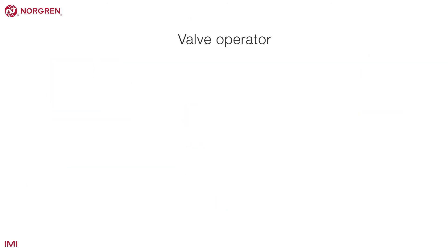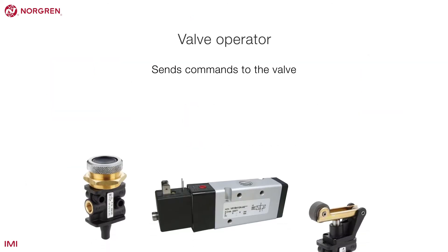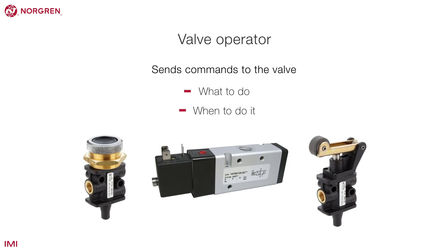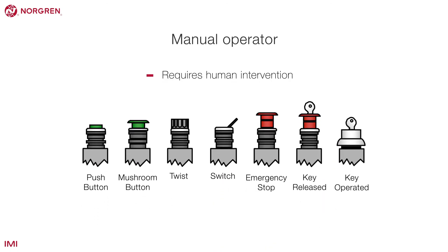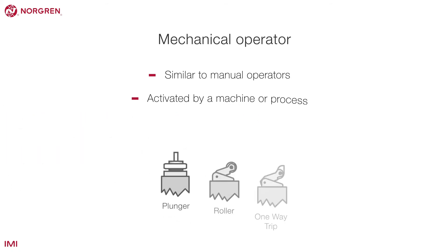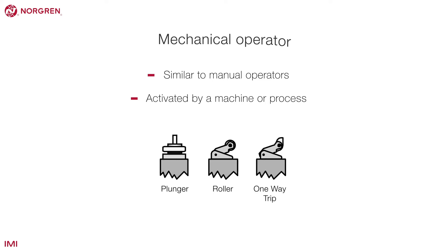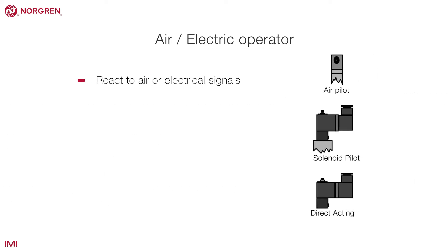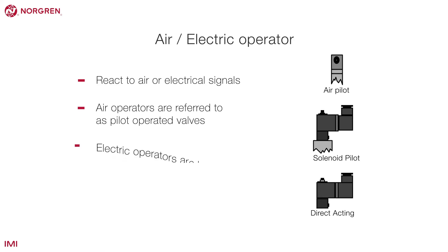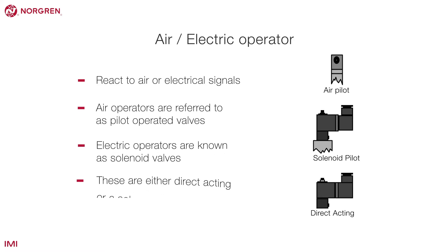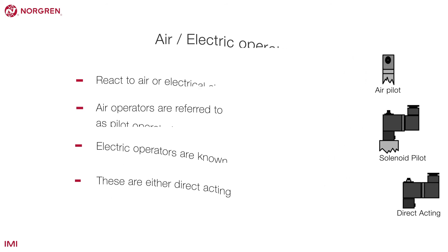A valve operator is the device that sends commands to the valve — it tells a valve what to do and when to do it. They fall into three categories: manual operators that require human intervention; mechanical operators that are similar to manual operators but are activated by a machine or process; and signalled operators that react to air or electrical signals. Air operators are referred to as pilot operated valves, while electric signalled operators are known as solenoid valves and are either direct acting or a solenoid pilot.